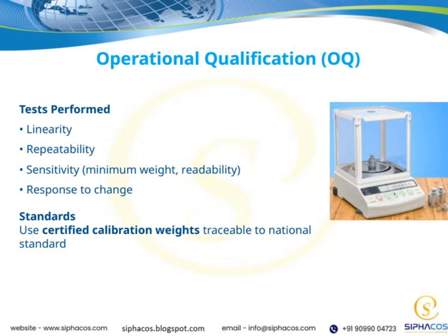All these tests are performed using certified calibration weights that are traceable to national standards. This traceability is fundamental because it guarantees that our calibration is accurate and universally recognized. In the context of overall quality assurance, these tests and standards help us verify that our equipment is functioning correctly and reliably before we move on to subsequent qualification phases.